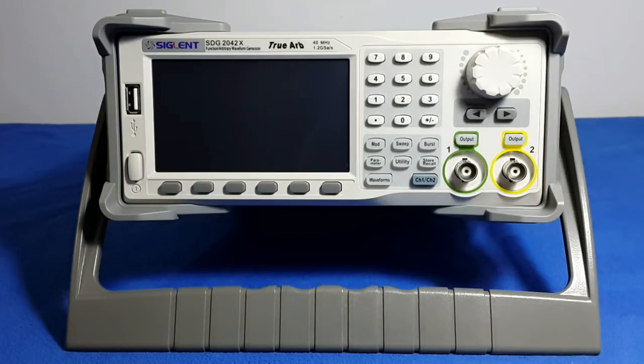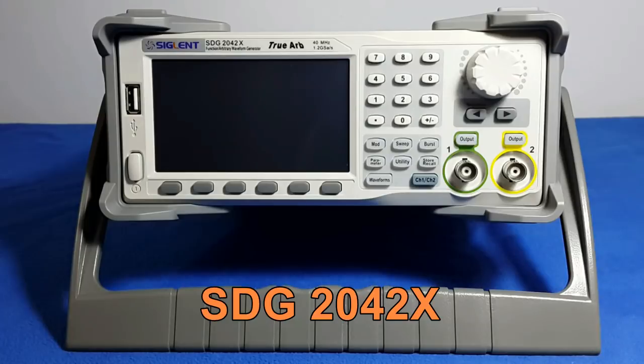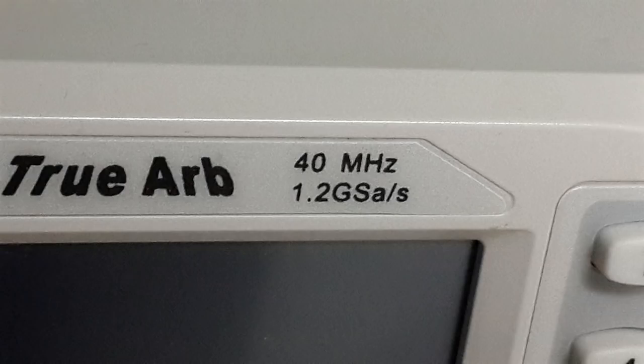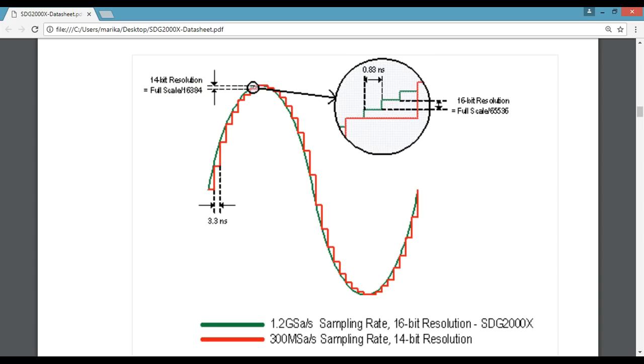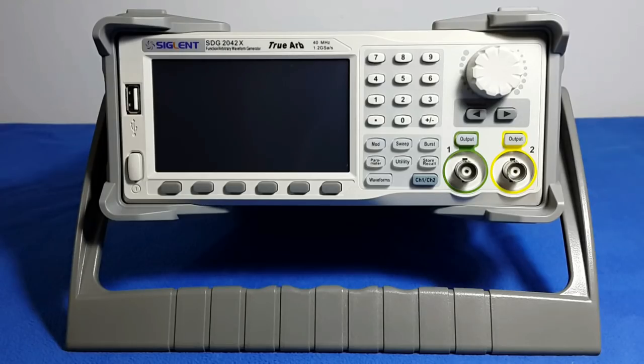There are three models in the market: 40 MHz, 80 MHz and 120 MHz, all of them with the same specifications, with 1.2 gigasamples per second and a vertical resolution of 16 bits. It's important to say that the arbitrary waves are also 16 bits too, up to 20 MHz and 75 megasamples per second.